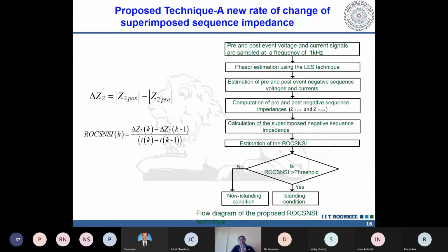This is known as Z2P, which is V2P divided by I2P at the renewable source terminal. We calculate these parameters at the renewable source terminal. After islanding, we calculate V2 island and I2 island, and from that Z2 island. The difference between these two is known as the superimposed component.